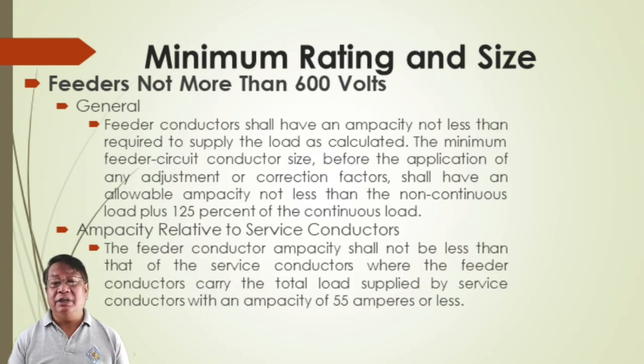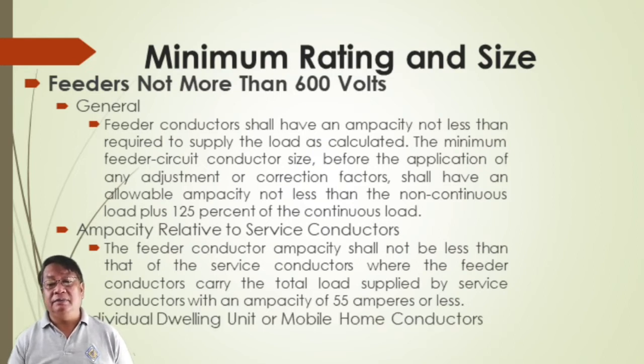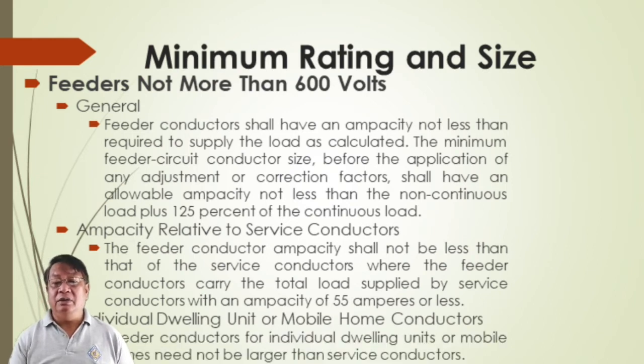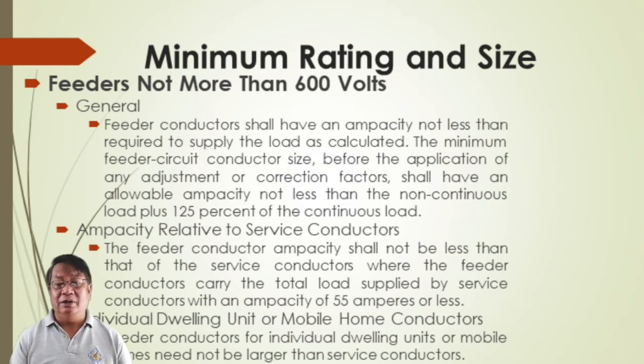Ampacity relative to service conductors: feeder conductor ampacity shall not be less than that of the service conductor where the feeder conductors carry the total load supplied by service conductor with ampacity of 55 amperes or less. For dwelling unit or mobile home conductors, feeder conductors need not be larger than service conductors, and should be coordinated with the service conductor rating.